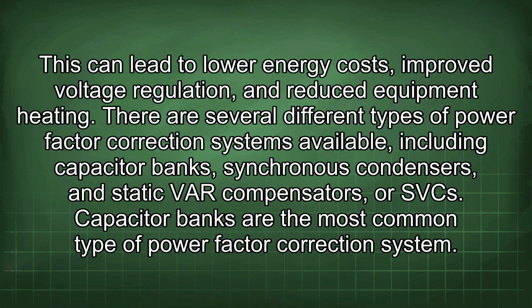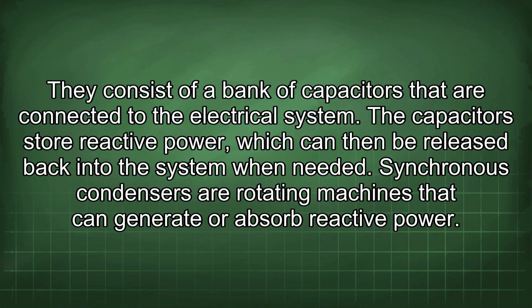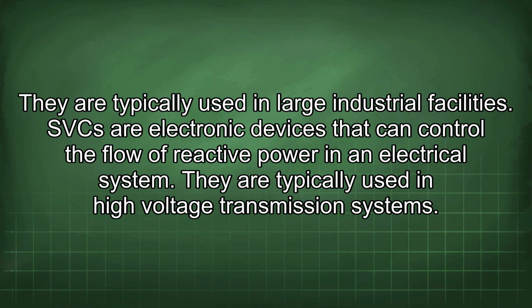There are several different types of power factor correction systems available, including capacitor banks, synchronous condensers, and static VAR compensators, or SVCs. Capacitor banks are the most common type of power factor correction system. They consist of a bank of capacitors that are connected to the electrical system. The capacitors store reactive power, which can then be released back into the system when needed. Synchronous condensers are rotating machines that can generate or absorb reactive power. They are typically used in large industrial facilities. SVCs are electronic devices that can control the flow of reactive power in an electrical system. They are typically used in high voltage transmission systems.